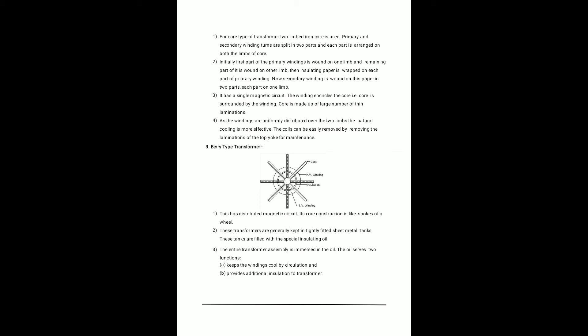Insulating paper is wrapped on each part of the primary winding, and then the secondary winding is wound over this paper in two parts, each part on a limb. It has a single magnetic circuit. The winding encircles the core and is made up of a large number of thin laminations. The windings are uniformly distributed over the two central limbs, allowing more effective natural cooling. The coils can be easily removed by removing the top yoke laminations for maintenance.